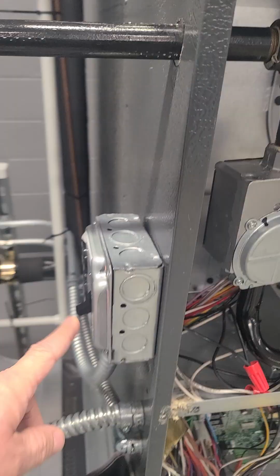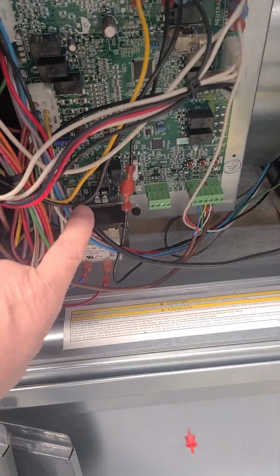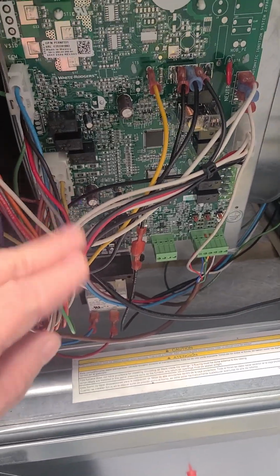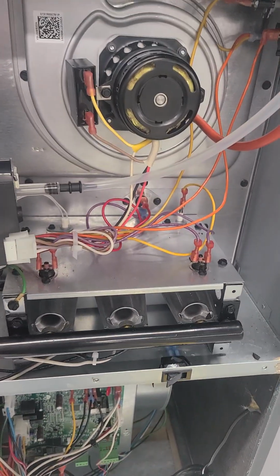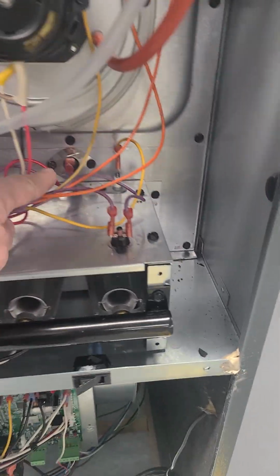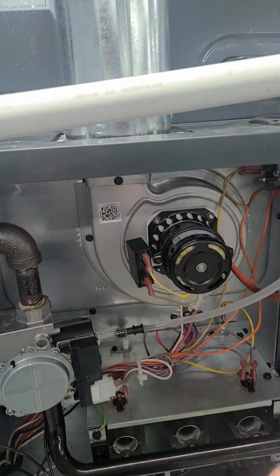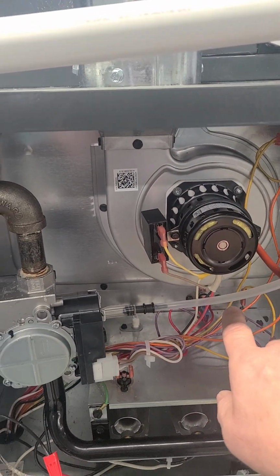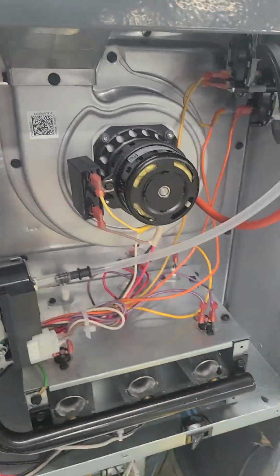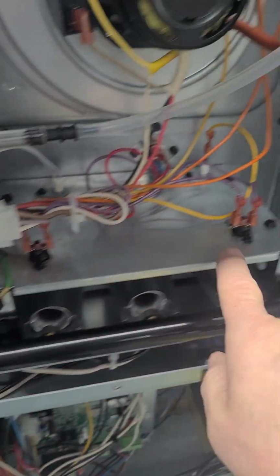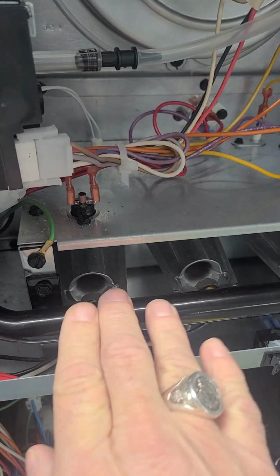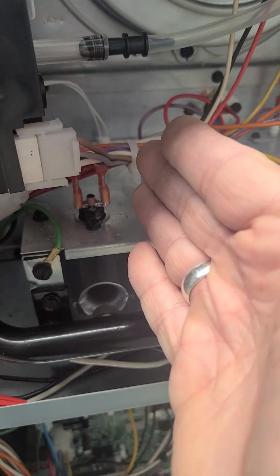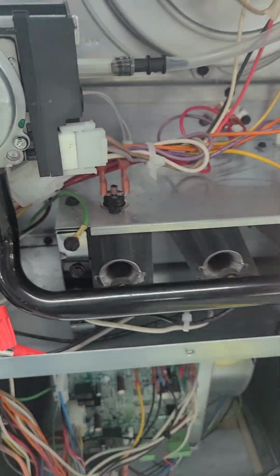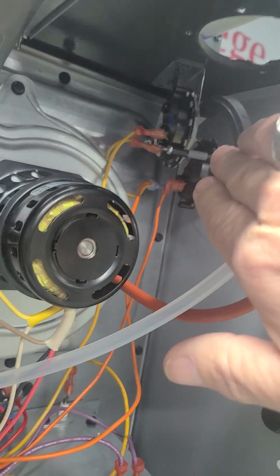Everything starts with 120 volts that gets supplied to the system board, where the system board has a control module that will continuously monitor all of the safety circuits in the furnace. Those include primary, now there's a hidden one, and auxiliary limit switches that are there in case there's a problem with the flow of air past the hot heat exchanger. In case that were to overheat, those limit switches will shut down the system to protect the system and the home. In addition, there are these flame rollout sensors that, if the flame from the burner doesn't go into the heat exchanger as it should and comes back, will trip, shutting things down as well. And then there are pressure switches for the flue.